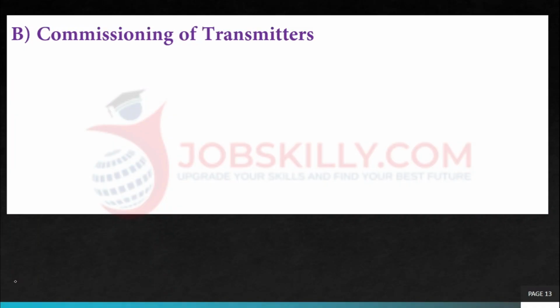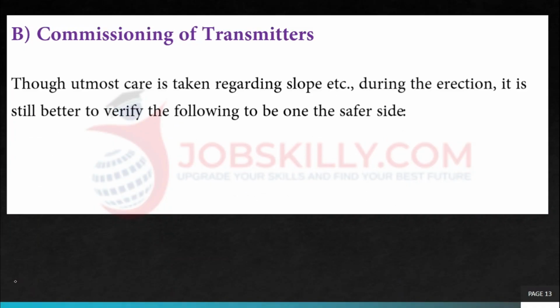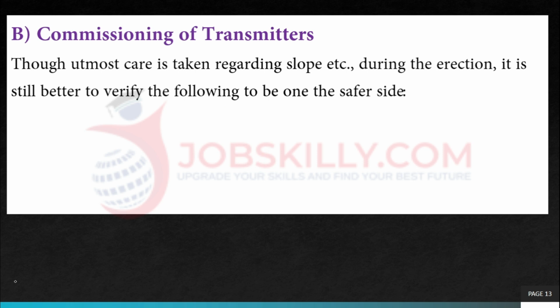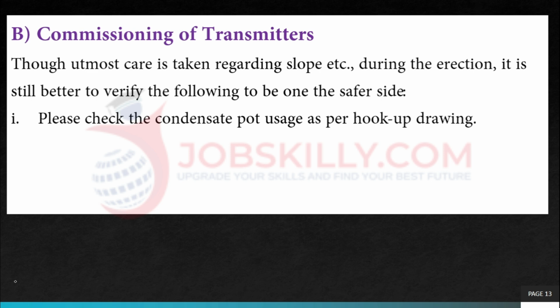We are going to learn now commissioning of transmitters. Though utmost care is taken regarding the slope of tubing or anything, during the erection we have taken the care of slope and everything, and it is still better to verify following to be on the safer side. Please check the condensate pot usage as per the hookup drawing. This is very important, and we have to check whether we have erected the condensate pot as per the hookup drawing or not.